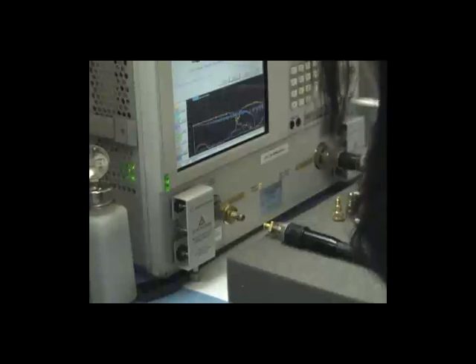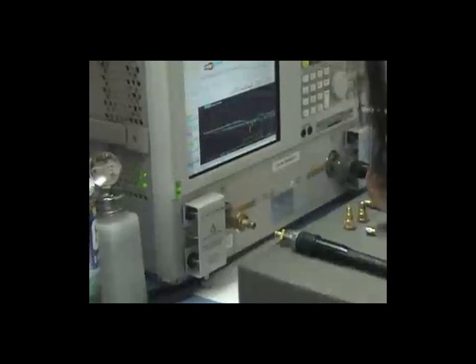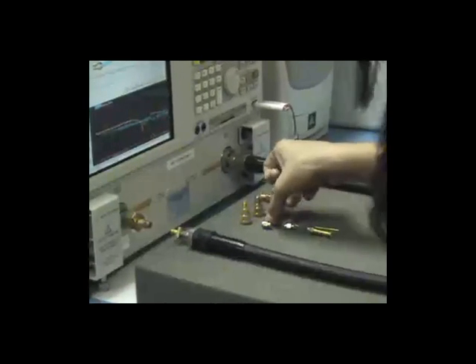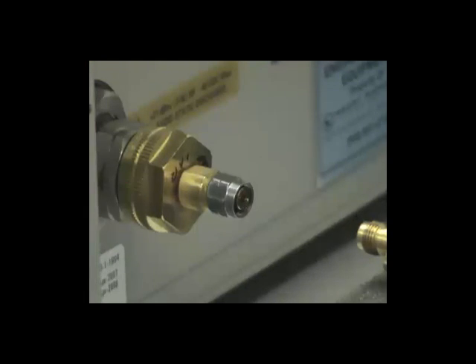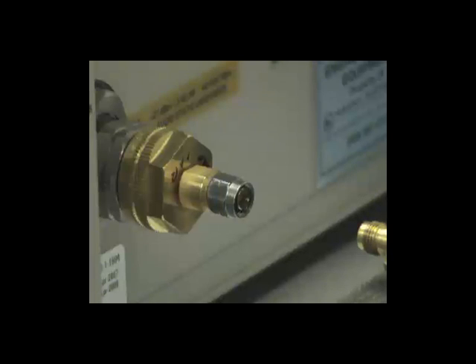Slide the cable a little towards the back so you have enough room to work with the airline. Before you go ahead and connect the contact onto the male pin here, you want to make sure that any static charge that has been developed on this center conductor by just sitting on this foam out here is discharged.